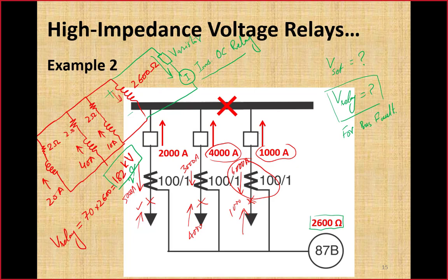But if a bus fault occurs through high impedance and the fault current is low, then this instantaneous branch would not be able to respond to that fault. In that condition, the overvoltage relay would respond and clear the fault. So this is the purpose of that parallel branch.